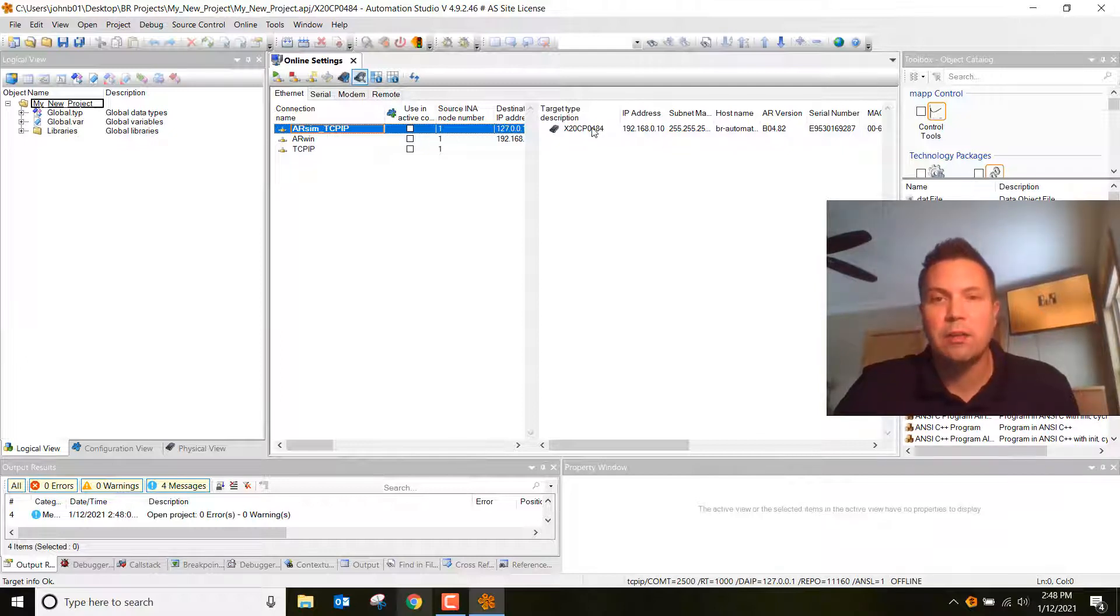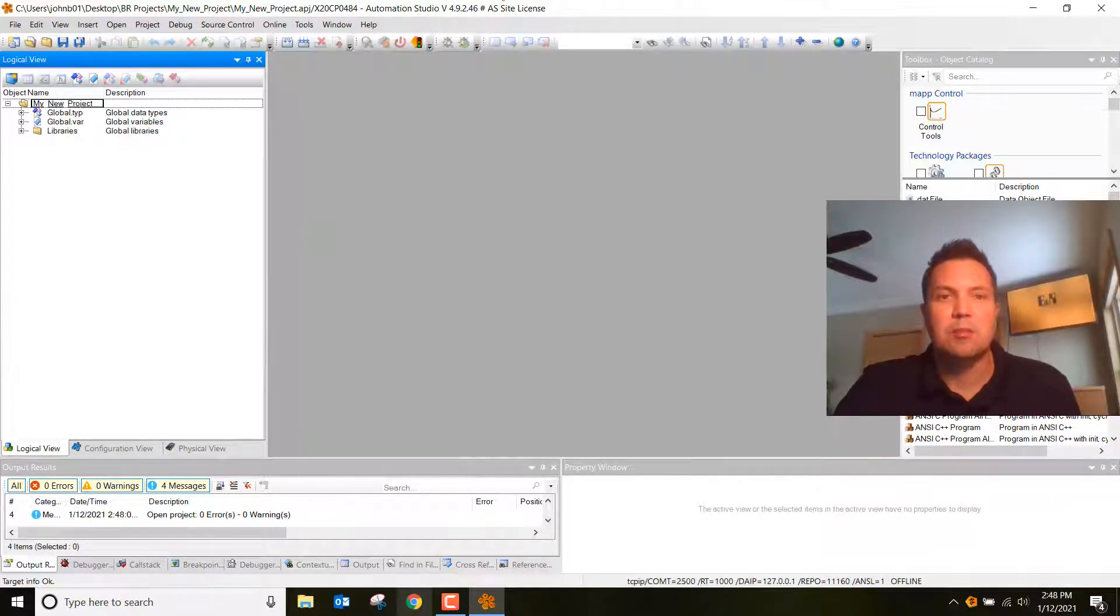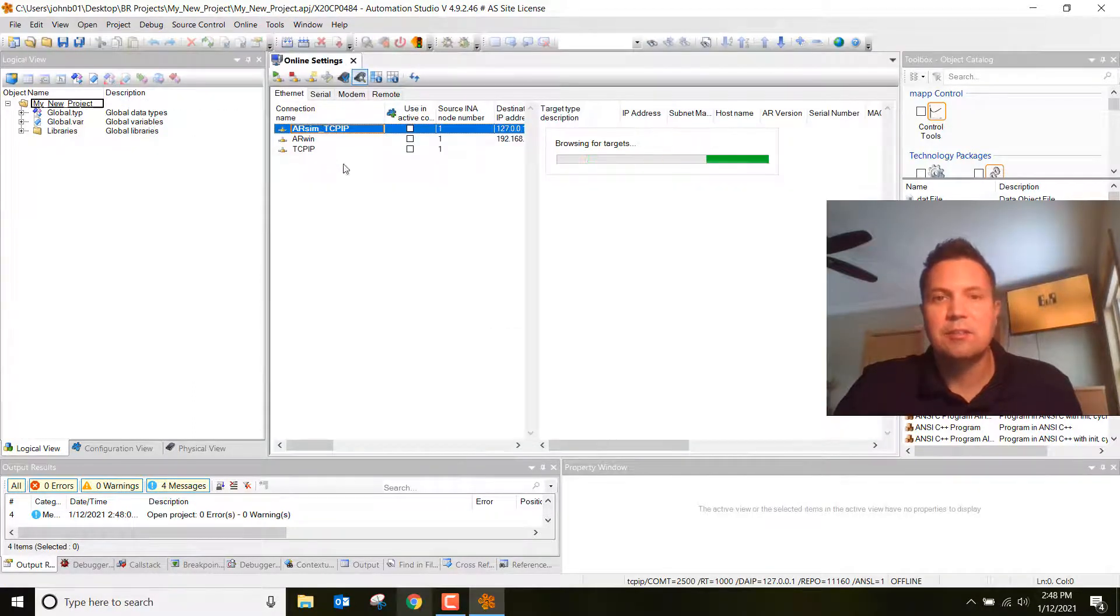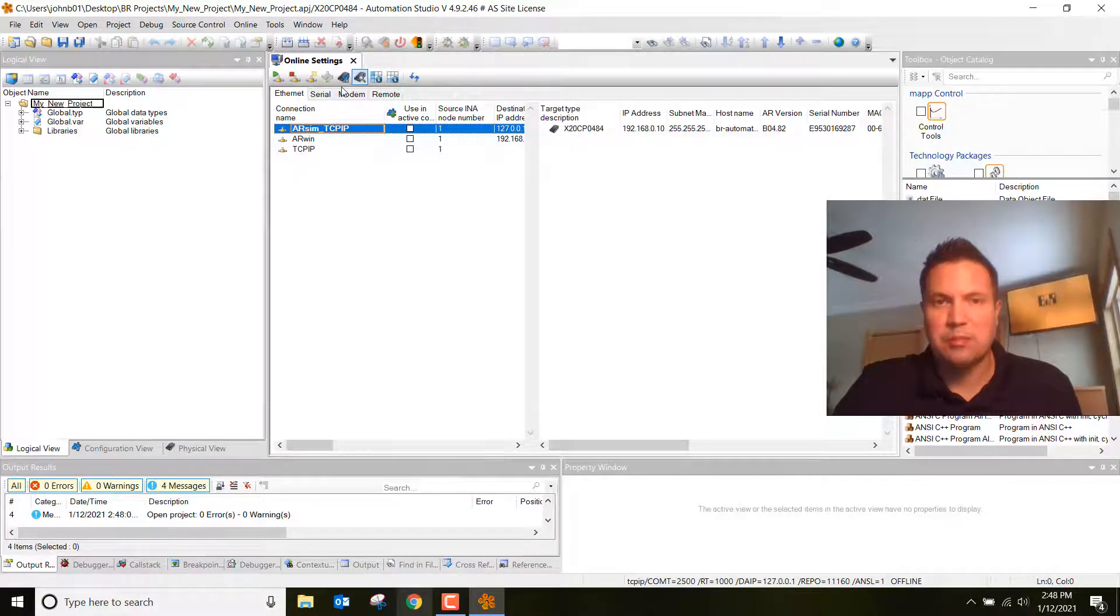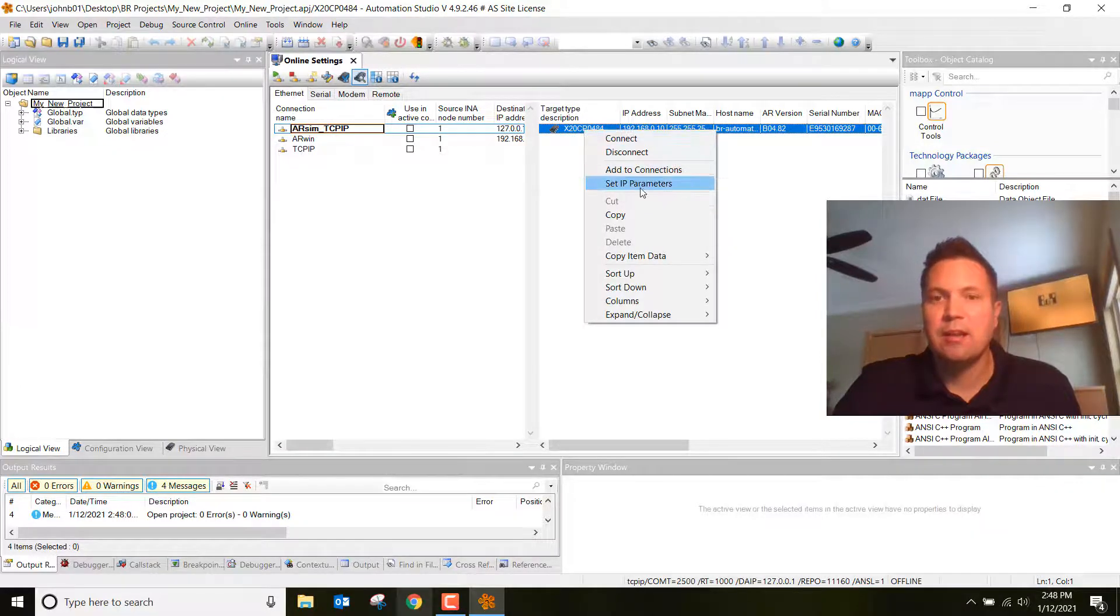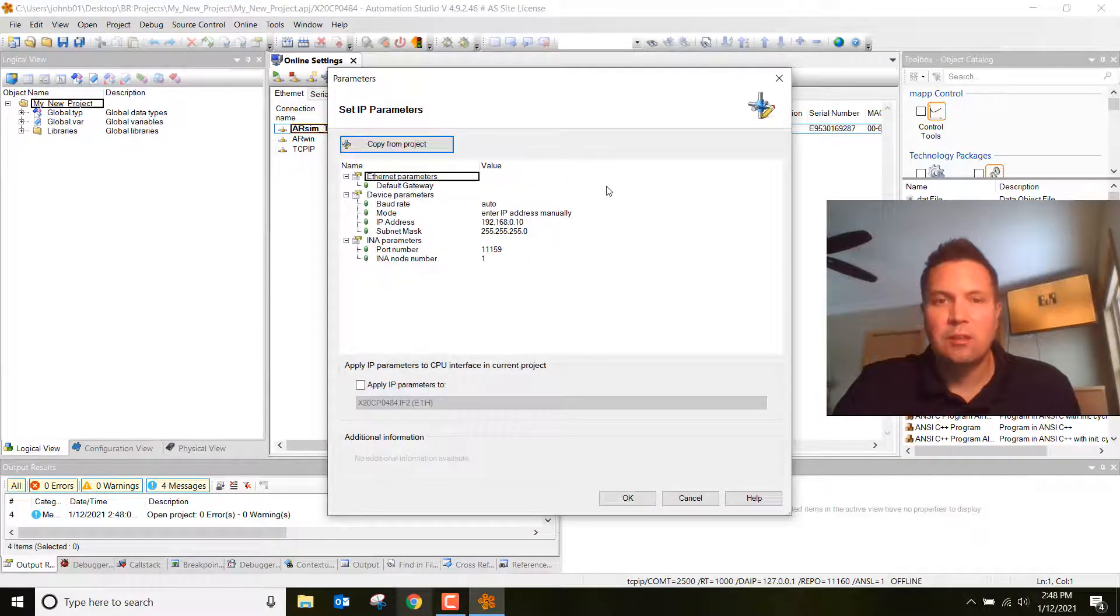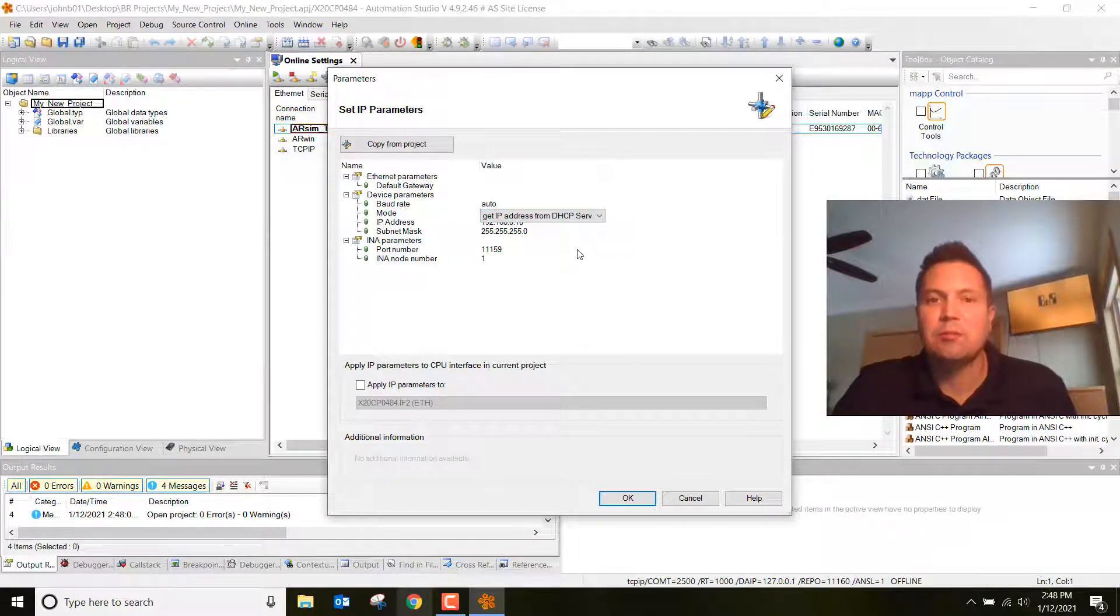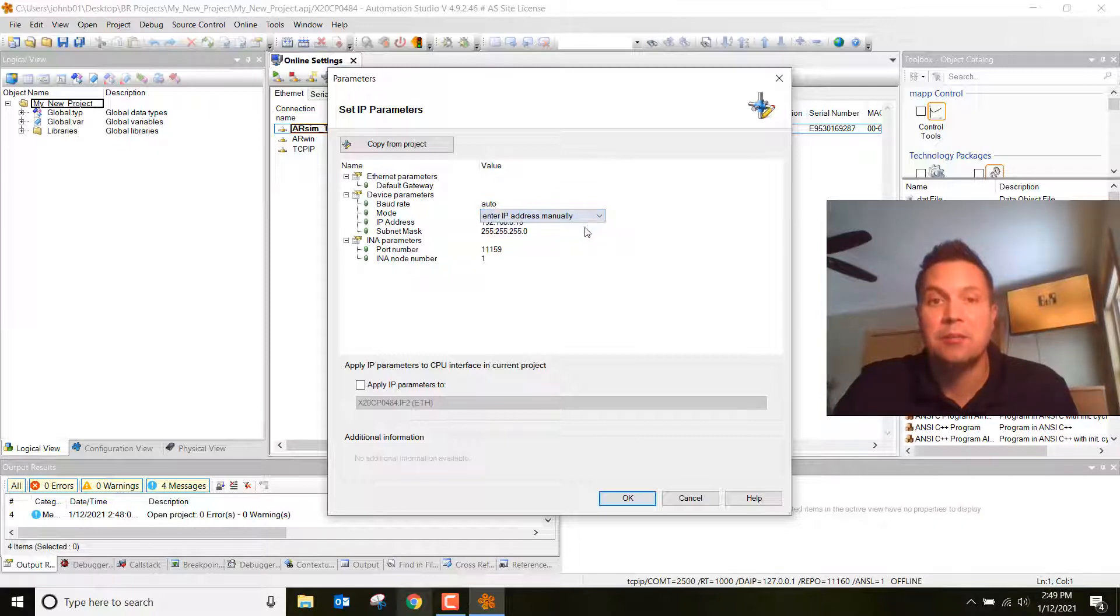Go ahead and right click on this, or actually what you're going to see is this will be blank or might show a picture of your controller. Go to online, click on settings, and it's going to open up this page that we were just looking at. Click on the X20CP 0484, right click on it, click set IP parameters. What you're going to see for the default is it's set as get IP address from DHCP server. We want to go ahead and click on enter IP address manually.